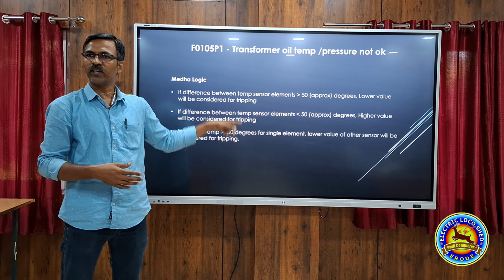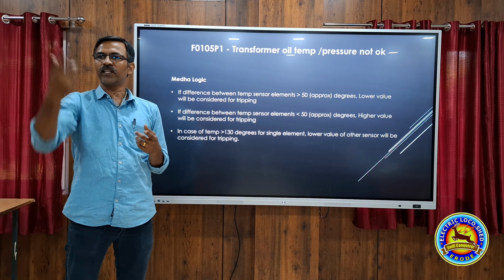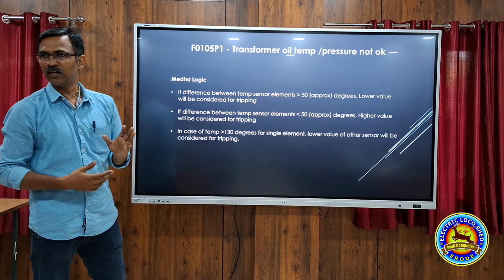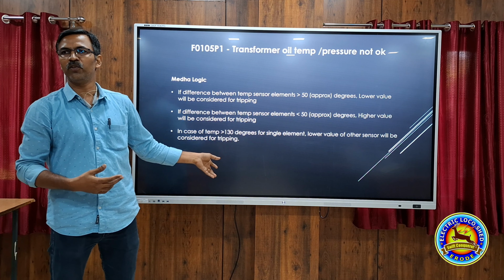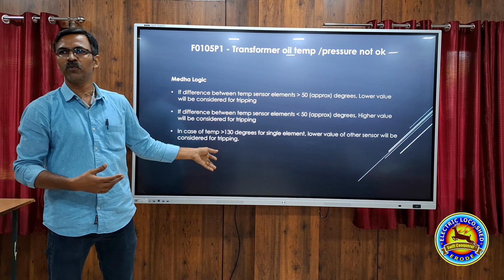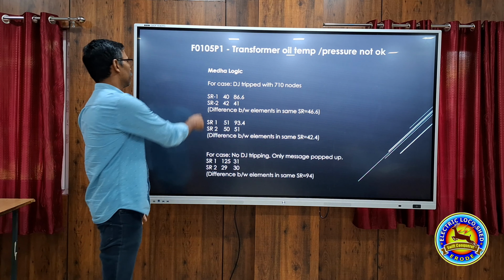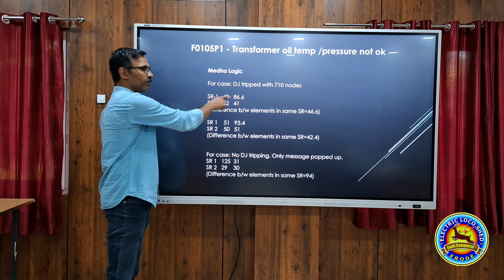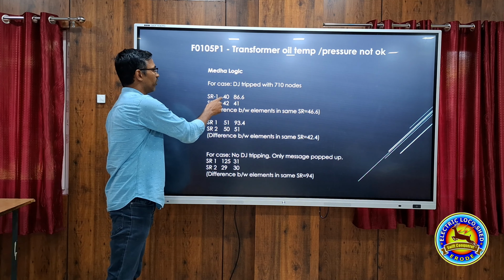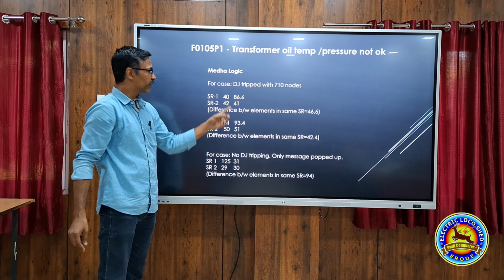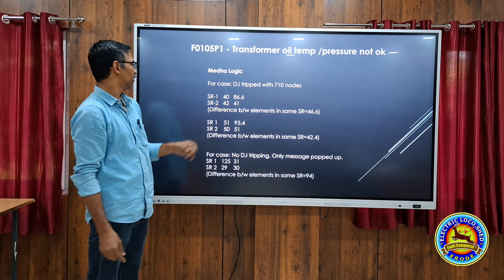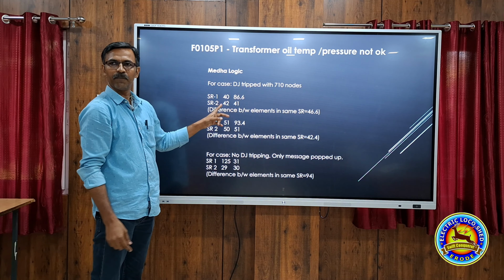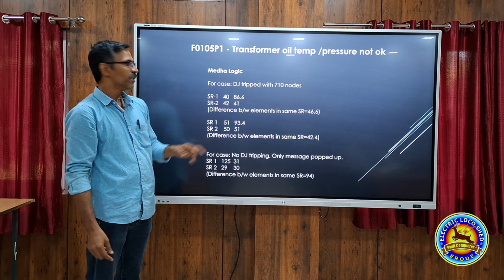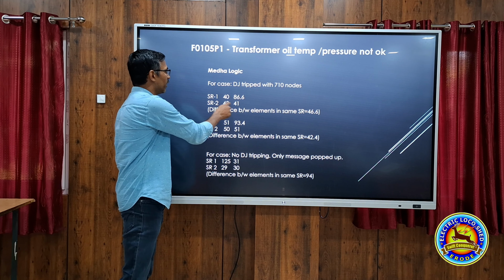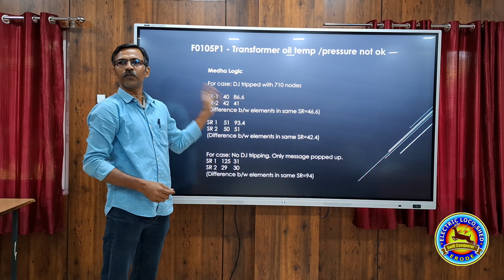In case of temperature, for any element, if the temperature goes beyond 130 degrees, that element will be discarded. The lower value from the other sensor will be taken. That's the Medha logic. These are some cases. So you can see in SR1 there are two elements. One is showing 40 degrees and another one showing 86.6 degrees. In SR2 it is almost the same, 42 and 41 degrees. So as you can see, the temperature is around 40 to 42 degrees only.